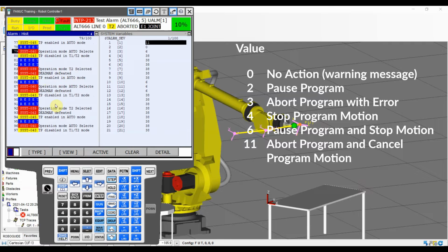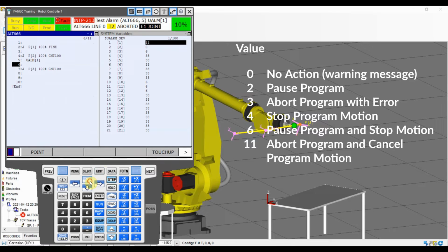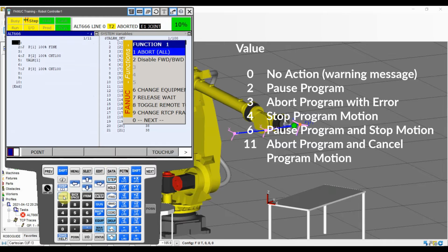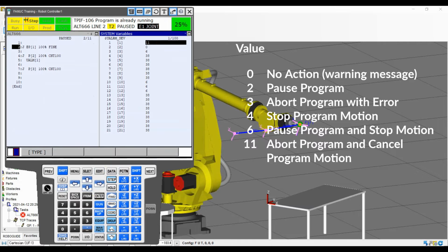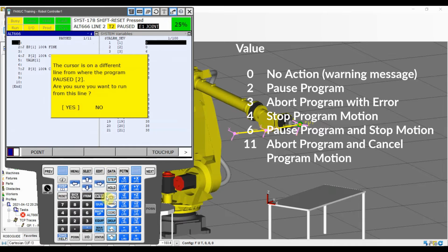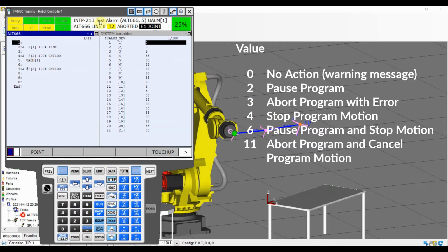And I want you to understand the importance of the alarms, because sometimes what can happen, and I've seen that many times, is you're going to have the robot running with a warning, and it will be stopped for any other reason, like a hold from the PLC or something else, and they will call you because there is an alarm in here.